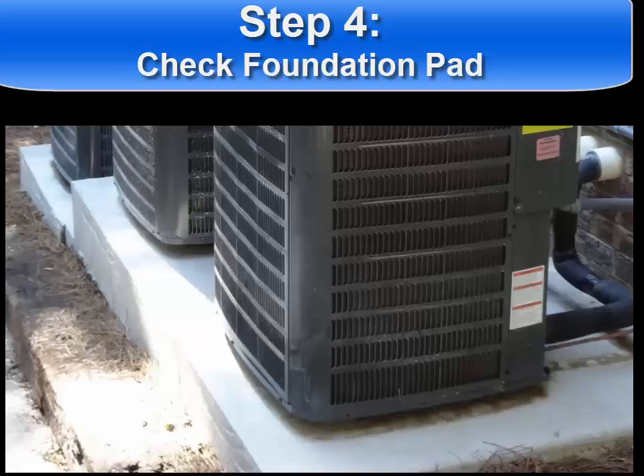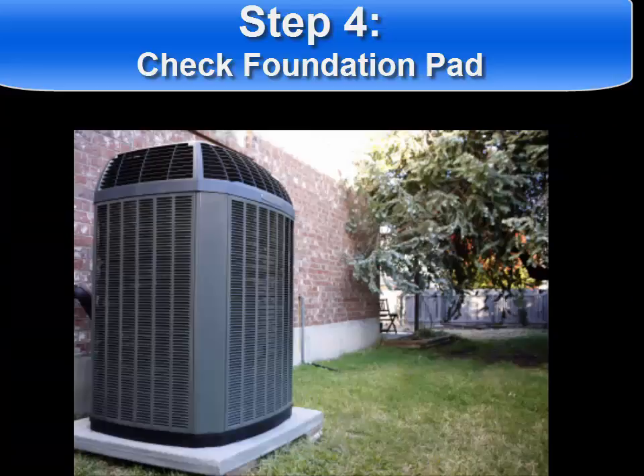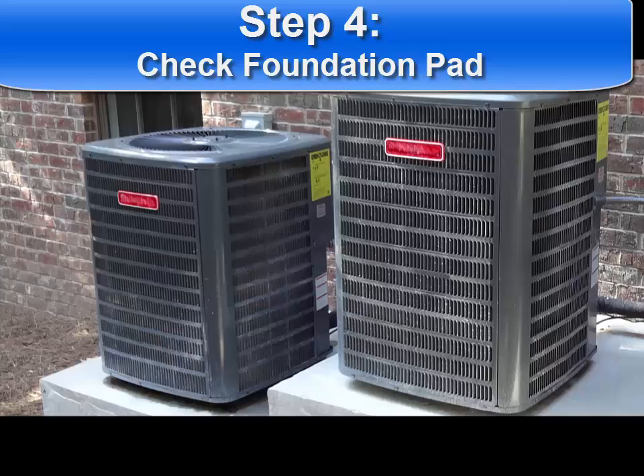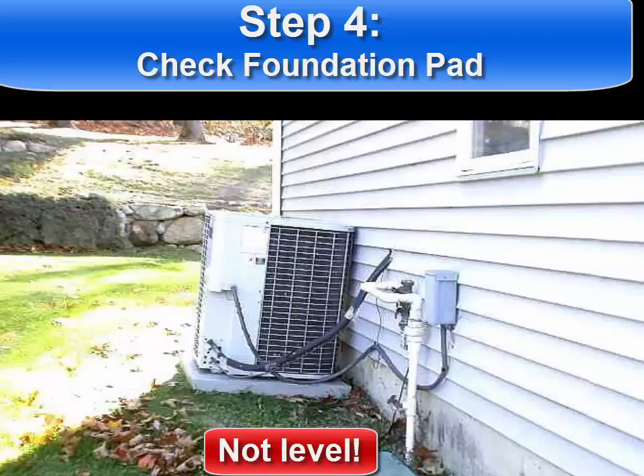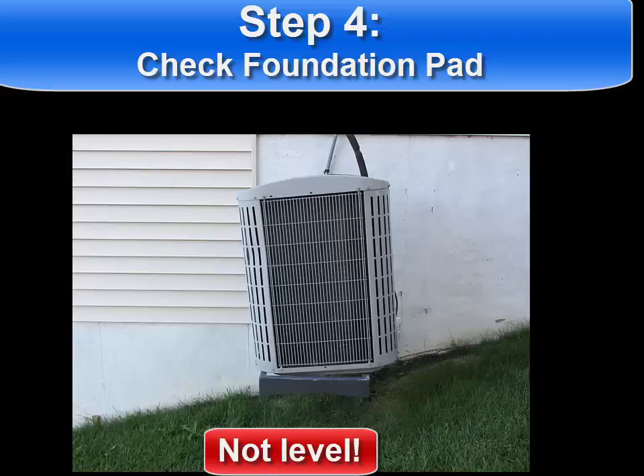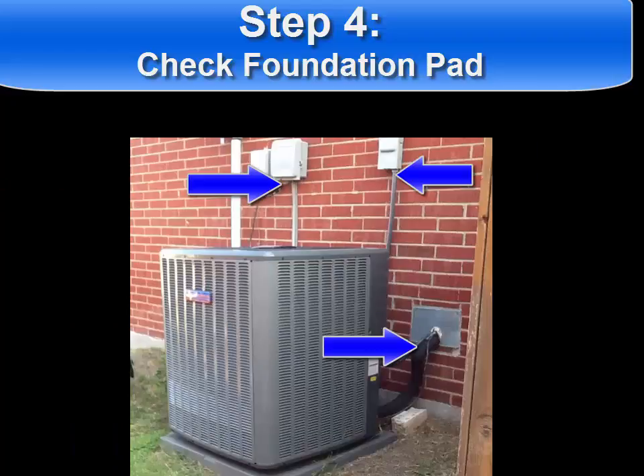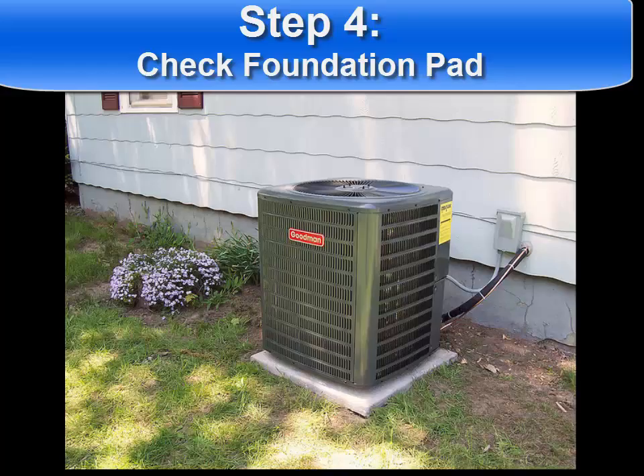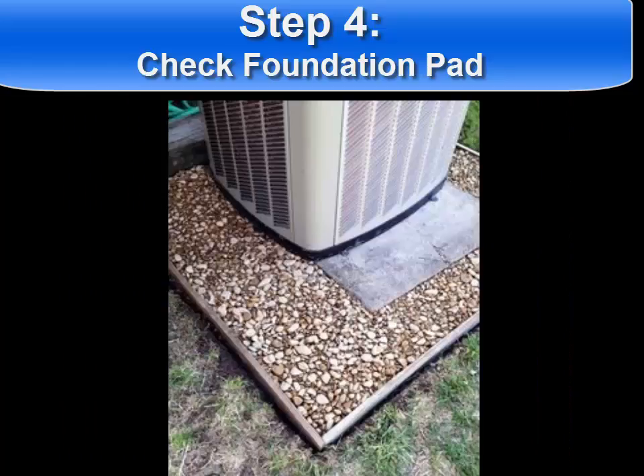Check to make sure the foundation upon which the outdoor unit sits is level. This is typically a concrete pad, but could also be plastic or rubber. Often, due to settling, corrosion, or drainage issues, these can crack, sink, or become unlevel. This puts strain on coolant lines and can bend or break copper or electrical lines, or cause water to puddle in the unit. Make sure the pad raises the unit out of the dirt and that there is adequate drainage around it so that water doesn't pool near it during a hard rain.